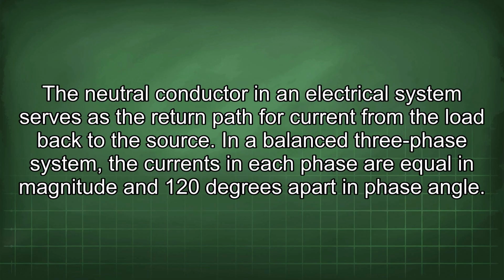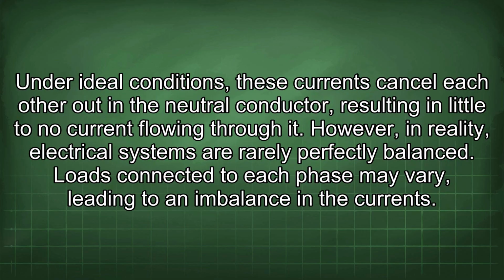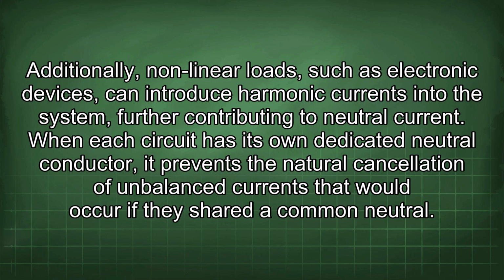The neutral conductor in an electrical system serves as the return path for current from the load back to the source. In a balanced three-phase system, the currents in each phase are equal in magnitude and 120 degrees apart in phase angle. Under ideal conditions, these currents cancel each other out in the neutral conductor, resulting in little to no current flowing through it. However, in reality, electrical systems are rarely perfectly balanced. Loads connected to each phase may vary, leading to an imbalance in the currents. Additionally, nonlinear loads such as electronic devices can introduce harmonic currents into the system, further contributing to neutral current.